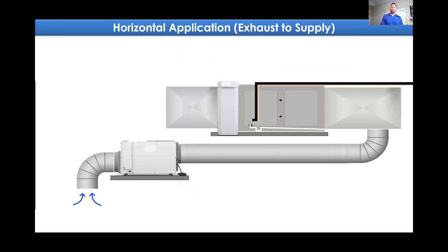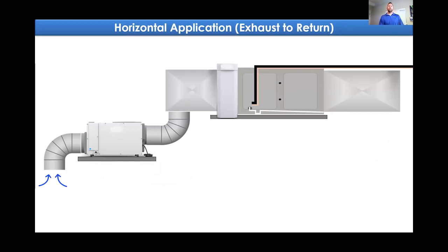How about a horizontal application? Attics, crawl spaces, South, Midwest, Kansas, that area there, up in the Pacific Northwest, if near the coastal environments, if you need it. Have the dehumidifier in an area where you can either duct it into the supply. Now, state of Florida, if you're in Florida, you cannot duct an exhaust of your dehumidifier into the return. It has to go to the supply. That's fine, no problem at all. We can definitely accommodate that. And that's a little bit what it would look like there. The rest of us in the United States could choose to put it into the return if we would like to. And that's up to application basis. That's up to the result of the performance of the system in working with your heating and cooling equipment. So you have those options of convertibility from supply or return.